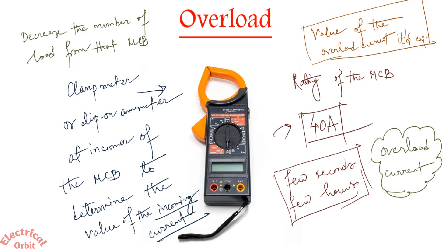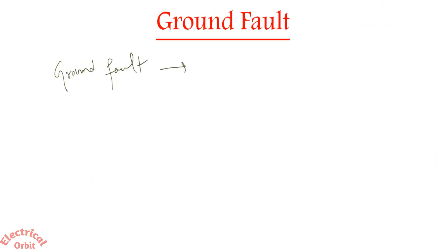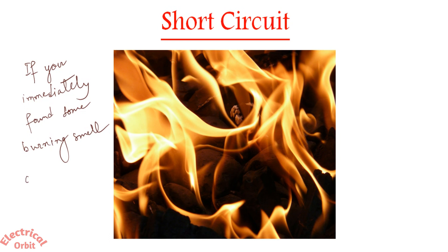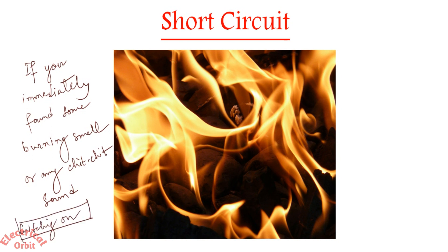For ground fault, you can use devices for detection of ground fault. For short circuit, if you immediately notice a burning smell or any crackling sound after switching on, there must be a short circuit occurring which is tripping the MCB frequently. Just clear that fault and your tripping problem will be resolved.